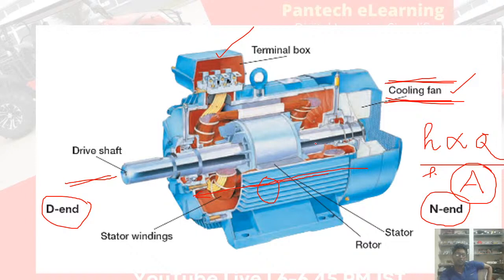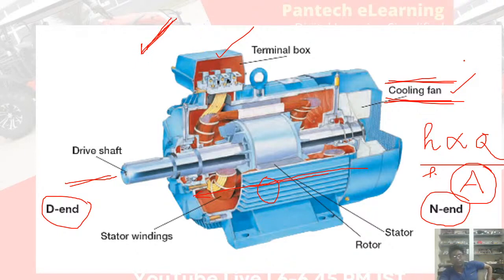The convective heat transfer coefficient, which is called h, is directly proportional to flow. If you increase the flow, your heat evacuation will be augmented. Convective heat transfer also depends on the surface area — that's why these fins are provided to extend the surface area, which is called extended surface heat transfer. These are the constructional features of the machine. As my teacher told me, motor control is an endless subject; all branches of engineering are involved — it's an ocean.